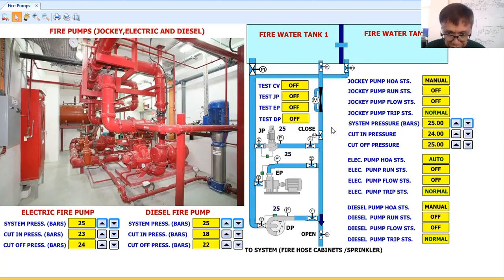As I said, first it will be tested at zero flow, meaning the discharge valve will be closed. Then your pump will run, and they will check the pressure in the suction and in the discharge. For the two pressures, they should pass the requirement as listed in the testing and commissioning form. Then after zero flow, they will test with 50% flow. We don't want the water to go to the system, to the fire hose and sprinkler, because we don't want to pressurize the system, and we don't want to burst the sprinkler. So they are closing this gate valve, then the water will be going back to the water tank.